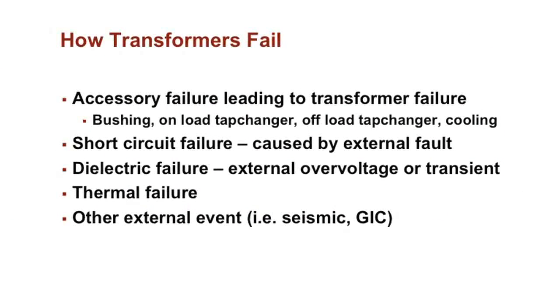Now, just to back up, how transformers fail. One of the main reasons transformers fail is because of an accessory. This could be a bushing or a tap changer. Another often way it fails is a short circuit failure. So there's some kind of fault on the system, and that comes back to the transformer, causes a mechanical stress in the transformer, and then fails it that way.